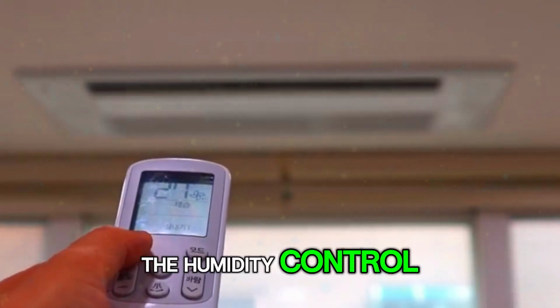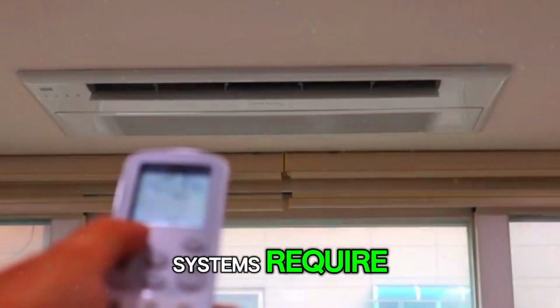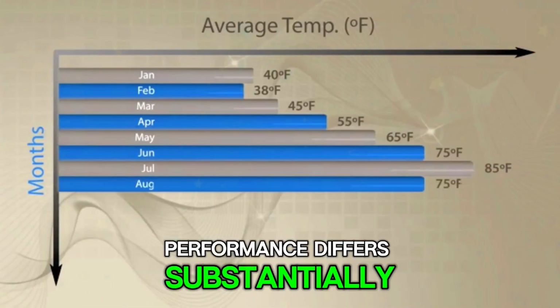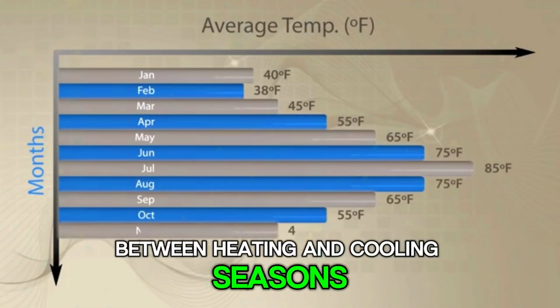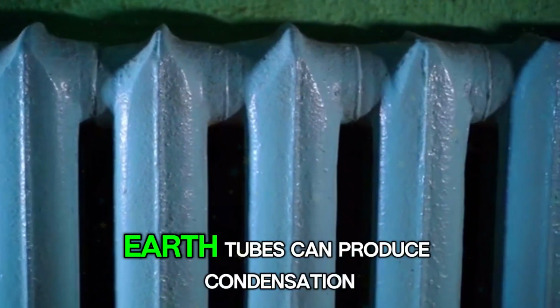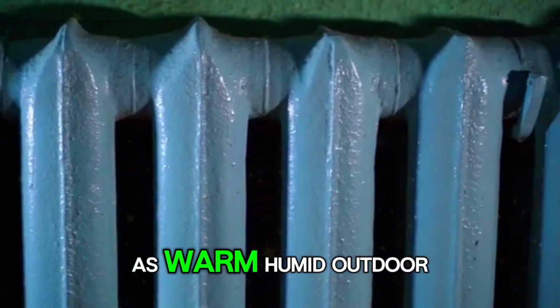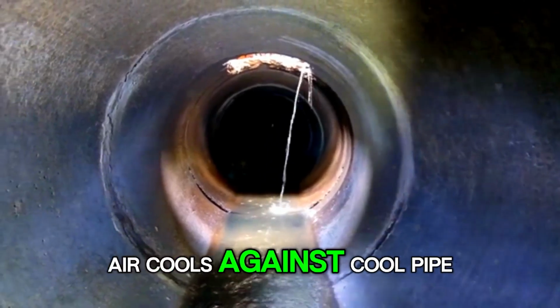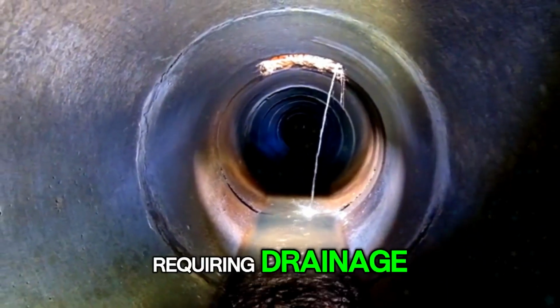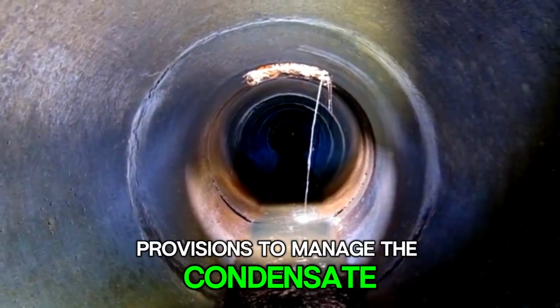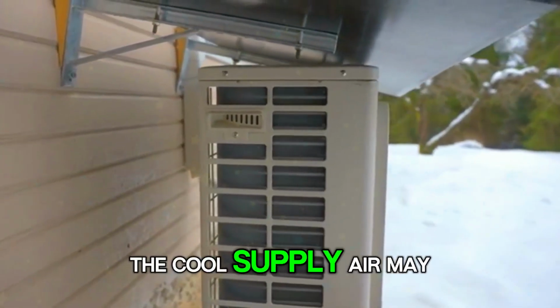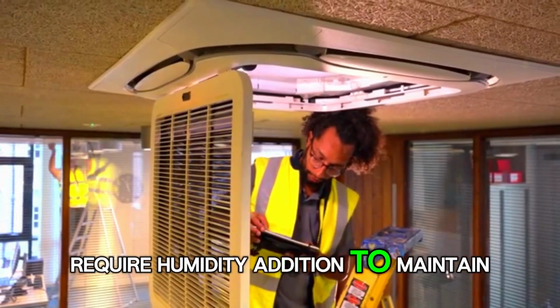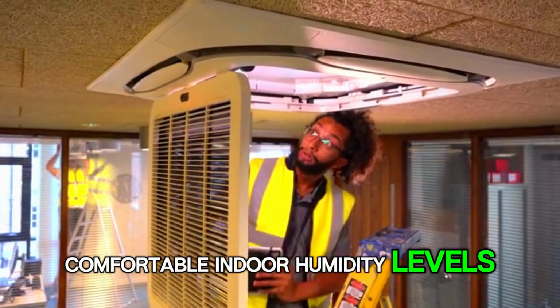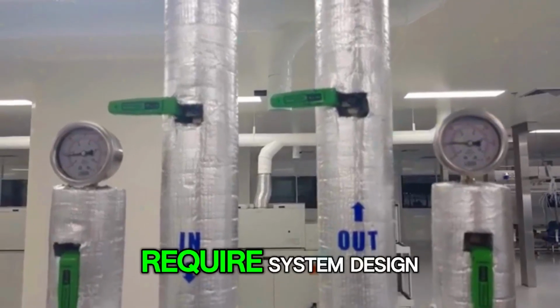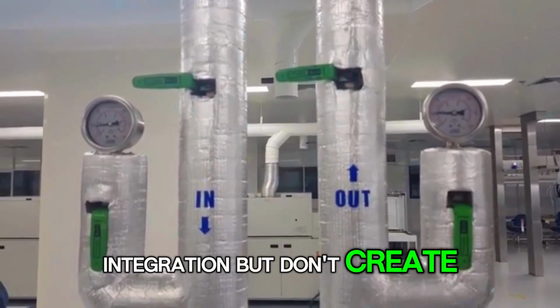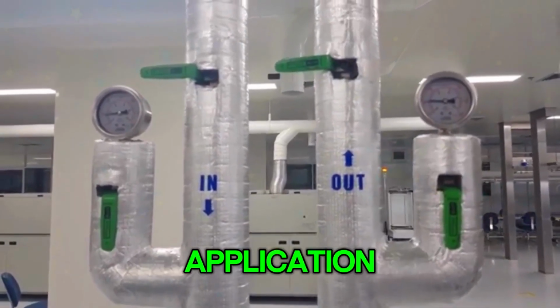The humidity control characteristics of earth tube systems require attention because performance differs substantially between heating and cooling seasons. During cooling seasons, earth tubes can produce condensation as warm, humid outdoor air cools against cool pipe surfaces, requiring drainage provisions to manage the condensate. During heating seasons, the cool supply air may require humidity addition to maintain comfortable indoor humidity levels. The humidity considerations require system design integration, but don't create insurmountable obstacles to effective application.